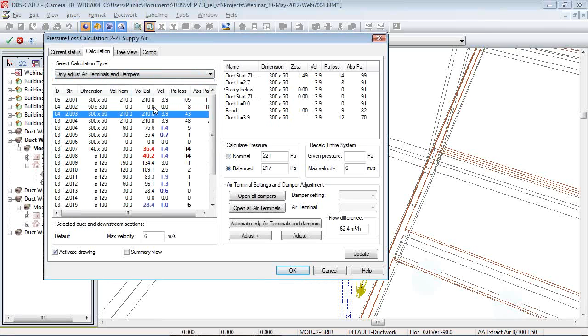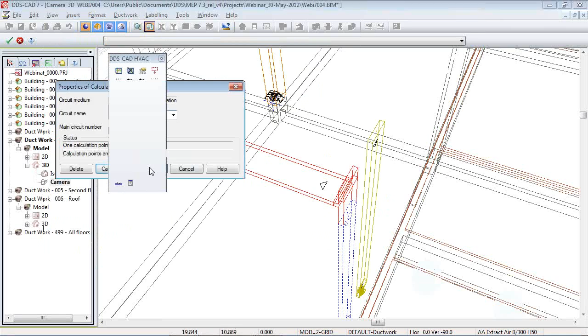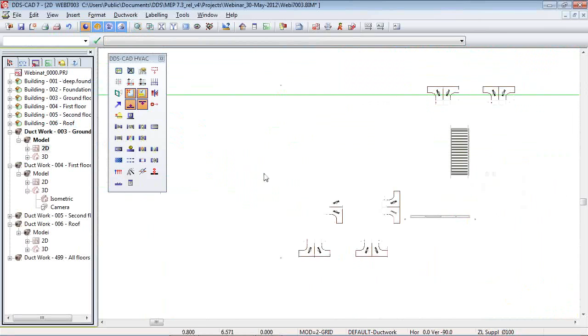But from the basis of my endpoints, for example, the velocity 6.5 is a result, and we can see that we are doing calculations based on a maximum velocity of 6. So this is what DDS tries to do in the calculation, or doing the optimization. So what I will do in this case is only adjust the air terminals and dampers.